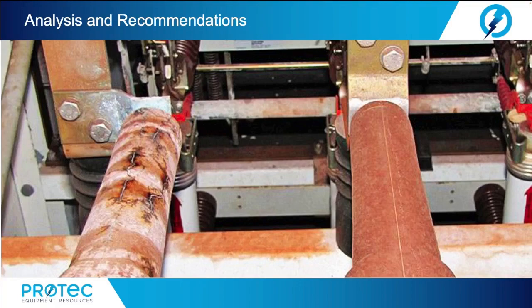Now, let's talk a little bit about analysis and recommendations. Many factors must be considered when assessing insulation quality, such as age, visual appearance, environmental conditions, partial discharge magnitude and partial discharge rate of change, partial discharge signature, and comparison of this data to similar insulation installations. Collectively, these factors will provide useful insight to the present condition of the insulation and its projected lifetime.